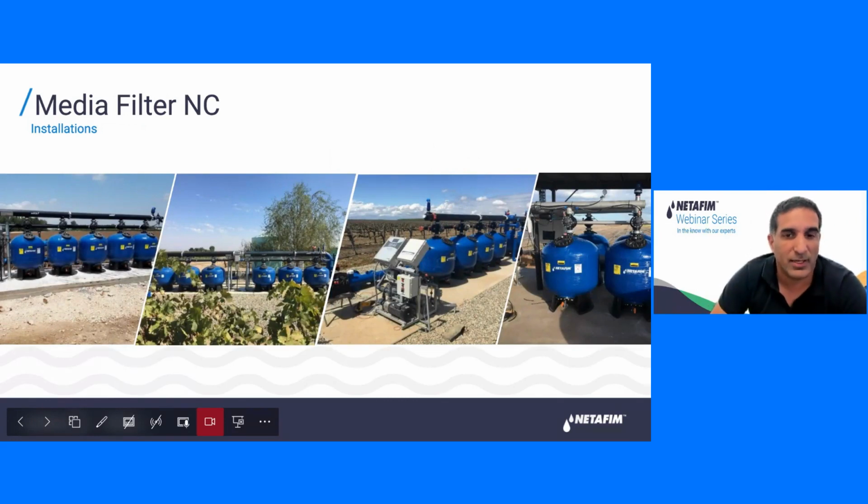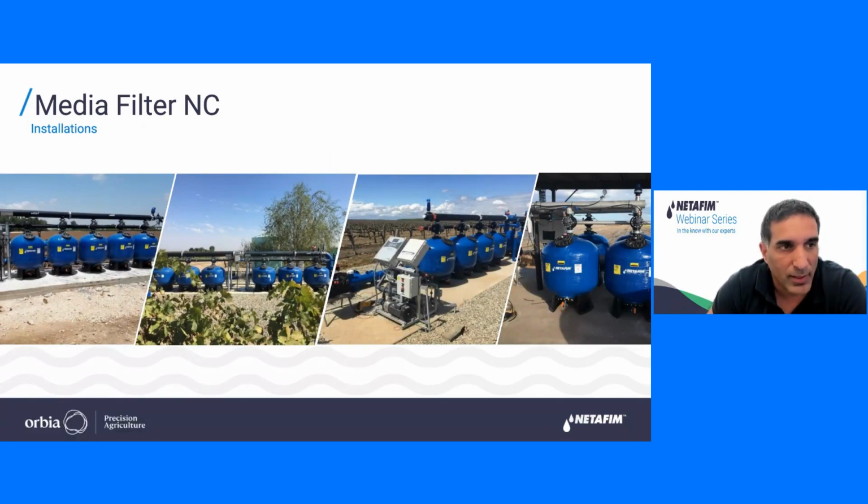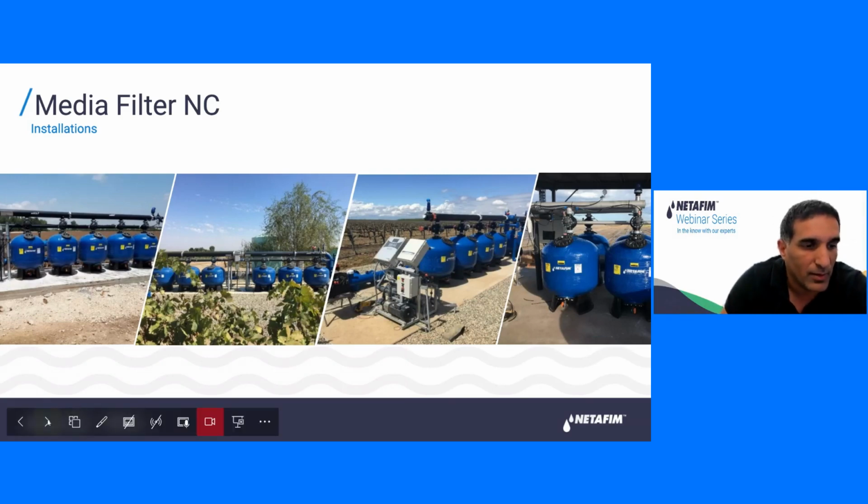Another product that sits inside the Sandstorm offering is the Sandstorm NC, or non-corrosive. Those are plastic tanks, PN6, with the same coating protection as we have in the metal, but since the system, including the manifolds, is offered with polymeric material, if we have corrosive water and a concern that the metal system will suffer from corrosion in a short time, this system is recommended, and it's also available. We have 36 and 48-inch tanks, and same as the metal systems, we can provide the design and the required system size per your requirements.